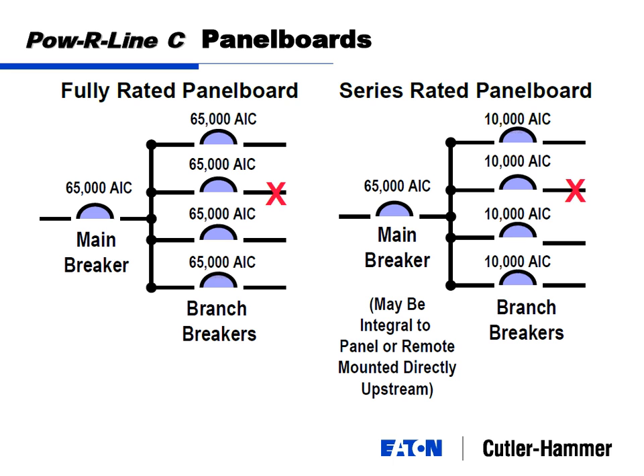we always recommend, I think UL and even NEMA recommend, test the breaker or replace the breaker. You know, just to make sure it still works. You don't put it into service and it's not working anymore. Even though it looks like it's in one piece, it may be something wrong on the inside.